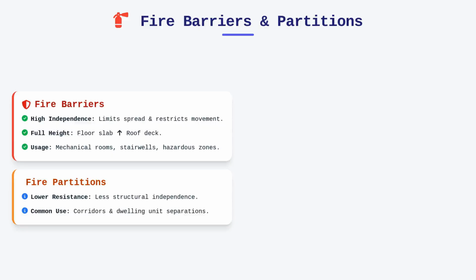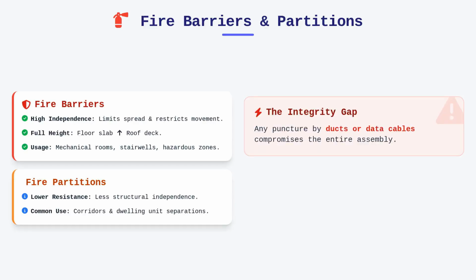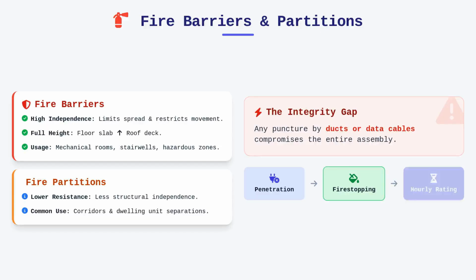The critical distinction here lies in their ability to maintain continuity. If a barrier or partition is punctured by a duct or a data cable, the integrity of the entire assembly is compromised unless properly protected. We must verify that every penetration is filled with an approved fire-stopping material that meets the same hourly rating as the assembly it occupies.